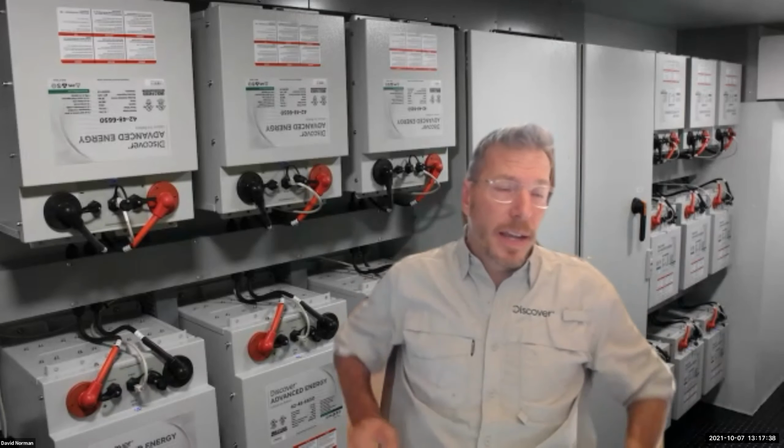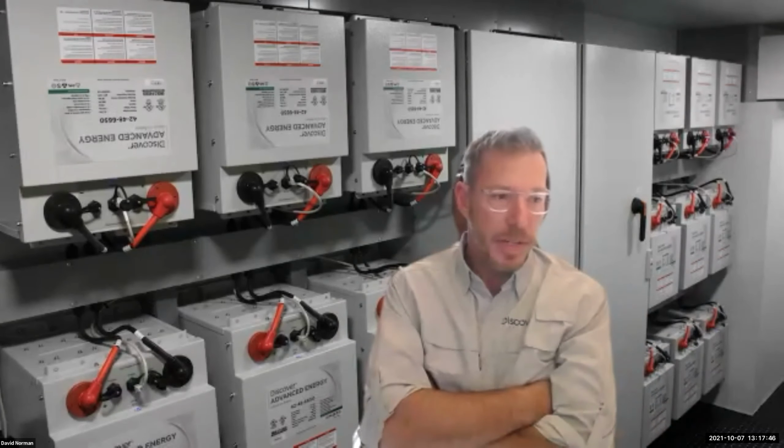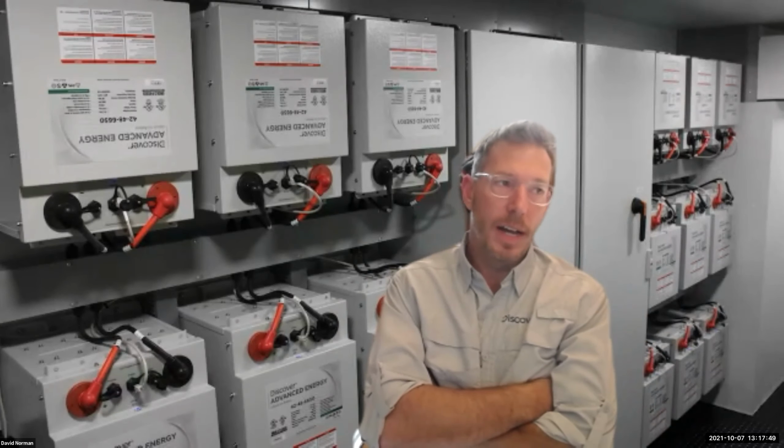This is important to say: it's not the external or ambient temperature, it's the temperature within the cell block that we're looking at. You can damage ferrophosphate or most lithium cells if you're charging them below 0 degrees C at that cell level. That said, we do have software and controls built in. You would have a UTP fault, under temperature protection, as opposed to HTP, which would be high temp protection. Essentially we would just open the circuit, allowing no discharge or charge from the battery.